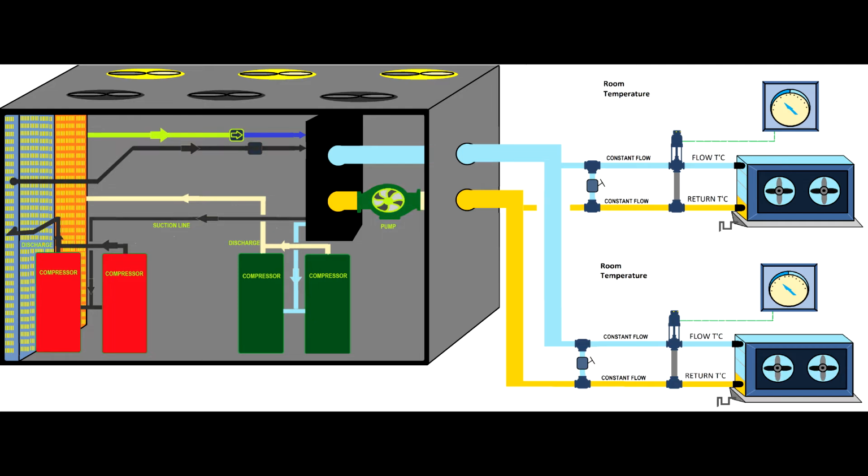So this is it with this type of fault. If you have proportional actuators, it will be a little bit of a nightmare. Go straight to the chiller, see if you have the right temperature on this heating agent, check the chiller, and then you will see further what you can do.